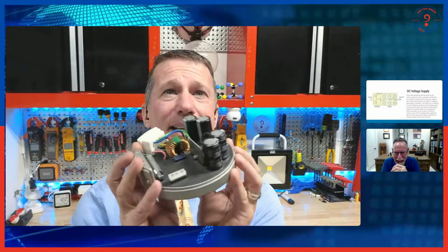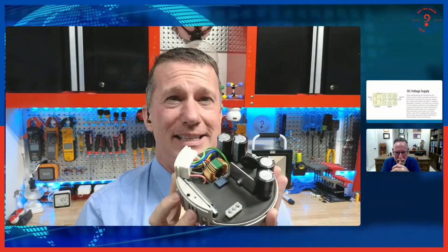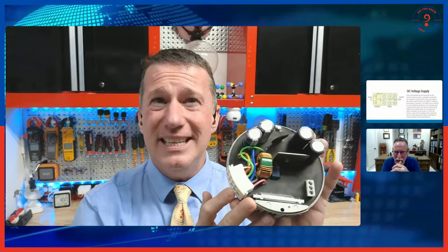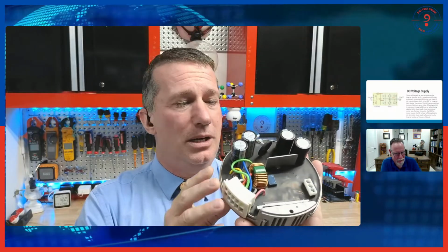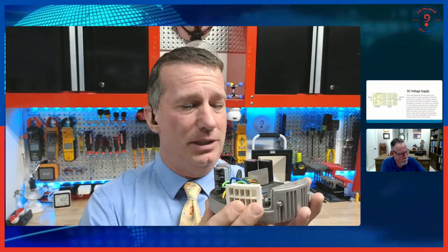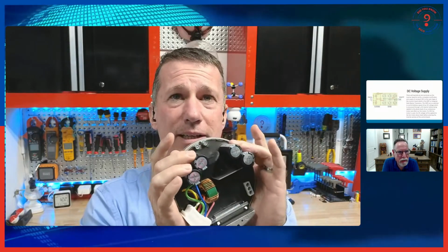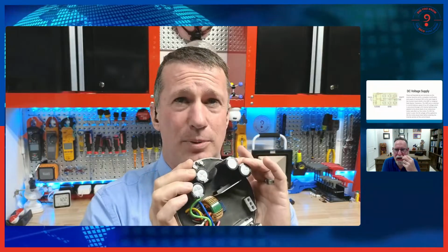Let's look at an ECM. I'd like to bring up what we're doing on an EC control for our motor. It's easy to call that an ECM motor, but it's actually redundant, electronically commutated motor. Think about what we're doing with our EC control on the back of an ECM, whether it's constant torque, constant airflow, or true variable speed. We're coming in with our constant supplied AC voltage, converting and storing it in DC. Unfortunately, we don't have test terminals on these, but it's the same principle as that inverter control board.